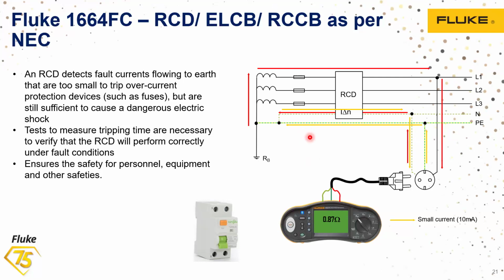Or if it is taking time to trip, that is also a real problem, because most of the time, if a 30 milliampere RCD is installed, it has to trip at 10 or 15 milliseconds, as recommended by the manufacturer. If it is not tripping at the specified time, what happens? If it is tripping at 100 milliseconds or 200 milliseconds, it is faulty equipment. So a faulty RCD has been installed, and we have to replace it.